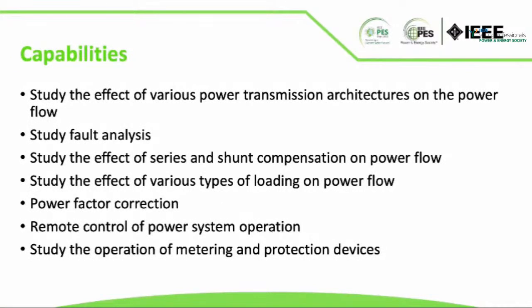So what are the capabilities of this SCADA arrangement? First, we can control the power transmission architecture. We can have different line lengths, different line resistance and inductance combinations, and we can study their effect on the power flow. We can also conduct all types of fault analysis on this arrangement. We have a sufficient protection system to protect the system during these fault conditions. So we can simulate a line to ground fault, a double line to ground fault, a triple line to ground fault, and the overcurrent and earth fault relays would be activated as protection devices.